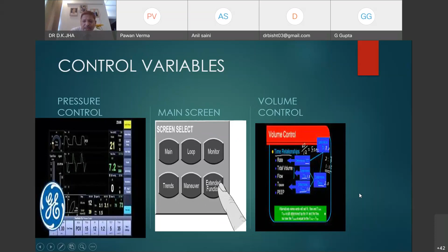Now, what are the phases of ventilation? What is trigger? Trigger is just the initiation of breathing. So what triggers the breathing? The patient triggers the breathing or the ventilator triggers the breathing. It is variable. So the patient triggers the breathing by flow or pressure set by the intensivist, or the machine triggers the breathing by time set by the intensivist.